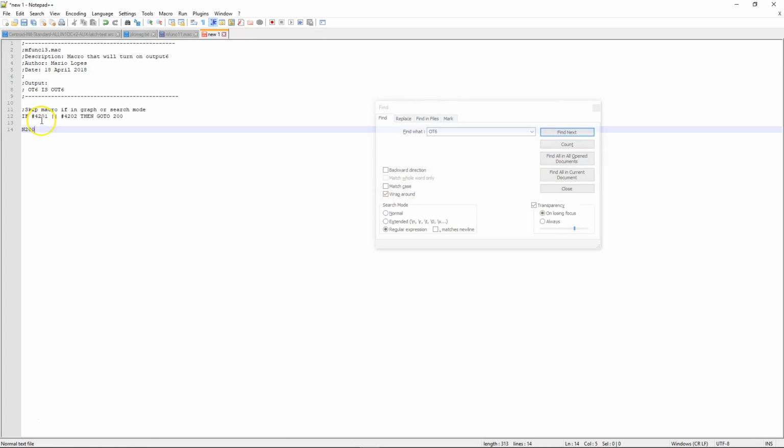All right, so here we are, we have that macro. Now, like I said, all we're going to end up doing is turn that bit on. So we're just going to say M94/13. That right there is going to send the request out. It's going to turn the 13th bit of this system variable associated with the M94, M95 callout, and we're going to modify the PLC program so that once that bit gets set, it's going to turn on that output. But this is all that the macro is going to do.